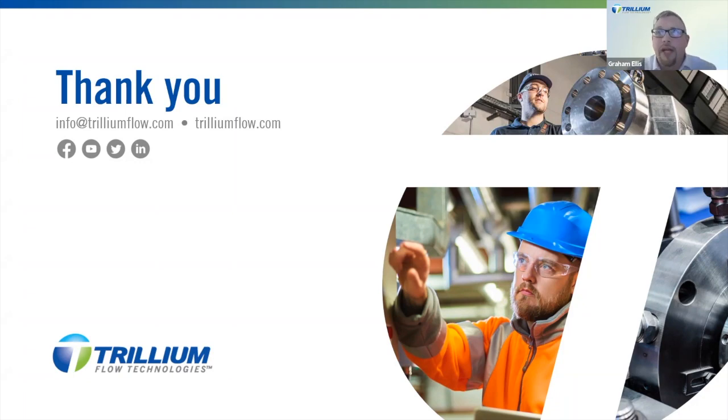Okay, and I've got one other question. How easy will this solution be implemented by customers? Sanket, I wonder if you could answer on that. What we have seen is using a bellow seal bonnet is basically standard practice in most molten salt applications. At first the customer might think twice about going for a bellowless bonnet, due to the performance of the valve. However, we have tested and validated the solution, which gives confidence that a bellowless bonnet solution can be considered, and it is probably the most cost-effective solution in the molten salt application.